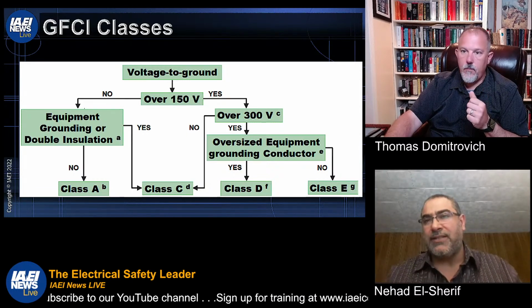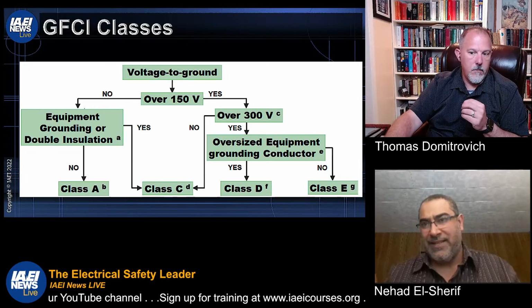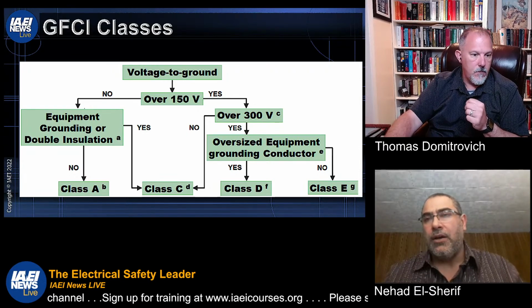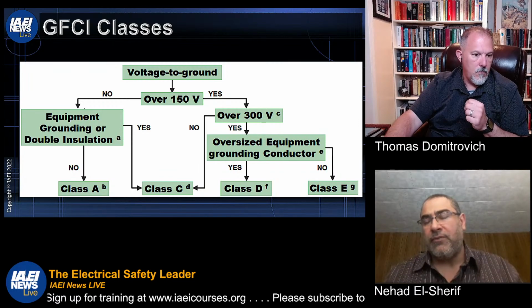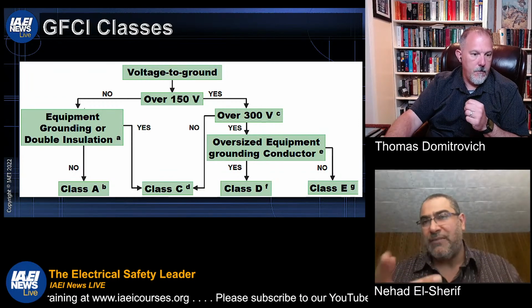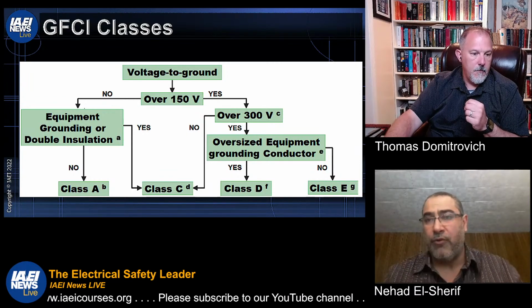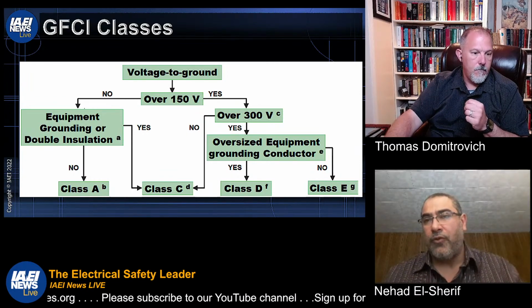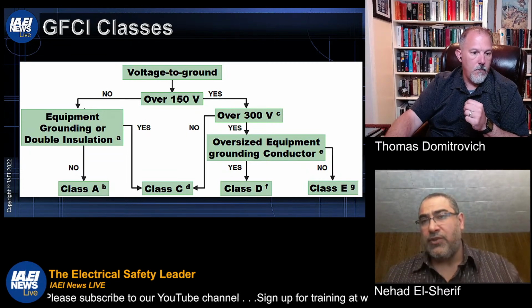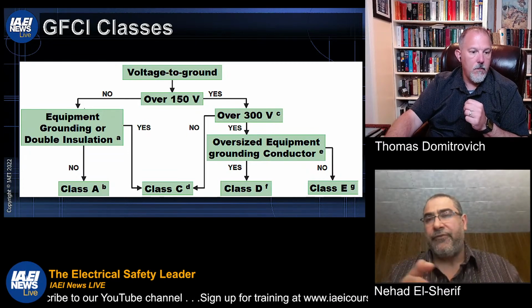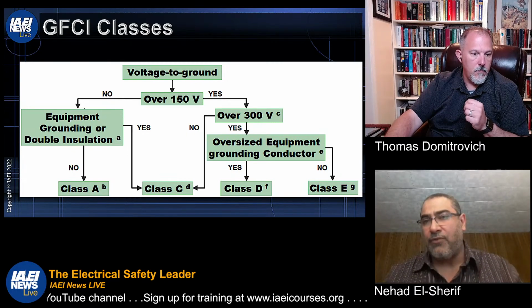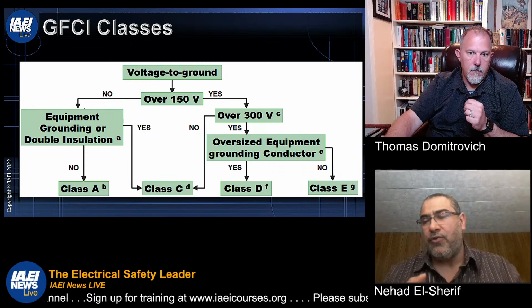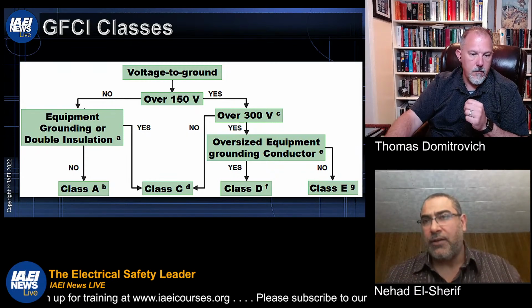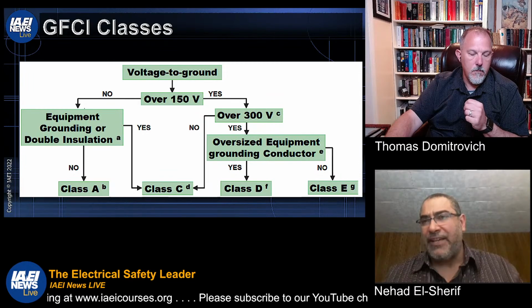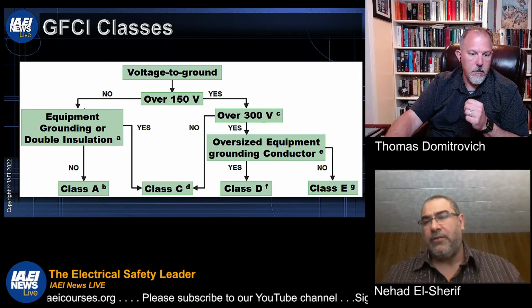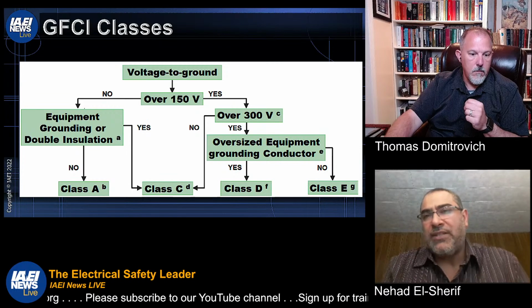This is where it gets into the special purpose area. There's no Class A that would meet this requirement. The maximum line-to-line voltage for a Class A is 240 volts, so it doesn't meet the more than 150 to ground requirement. So if you have over 300 volts to ground, this would be D and E. But if you have less than 300 volts to ground, this will be Class C, which is simply, let's say, the 2.8 applications. Anything where your voltage to ground is less than 300 volts.